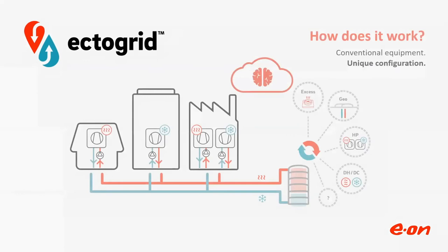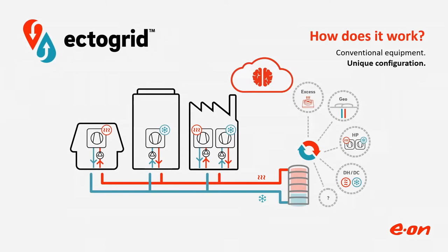So Ectogrid, how does it work? On the picture here, we have houses with a mixture of heating and cooling need. For instance, the building to the left is having heating need. They have a heat pump. The heat pump will fetch hot from the hot pipe and give away cold to the cold pipe. The neighbor building in the middle is having a cooling need. It will fetch cold from the cold pipe and give away hot to the hot pipe. Again, it's not really hot. It's more lukewarm, we could say.